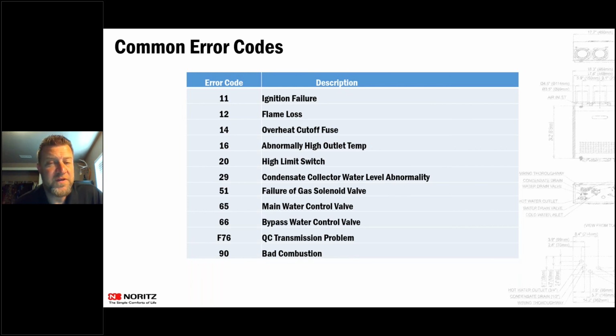So 12 is a flame loss, which means it lit, the flame sensor saw flame, but then the flame went out. Typically with a 12 error code, it is either one, it doesn't have enough combustion air, or two, the gas supply is too small, so they don't have enough gas coming into the unit, or the inches of water column got below the set point.